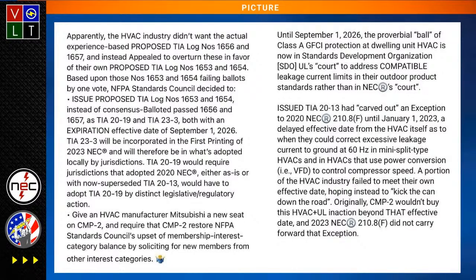Let me explain how this works. They have a UL standard. That HVAC equipment is installed by that UL standard, it's designed by that UL standard. It's not designed by Code Making Panel 2 arbitrarily deciding, you know what, we want Class A GFCI protection there, and guess what, y'all are going to fix it.